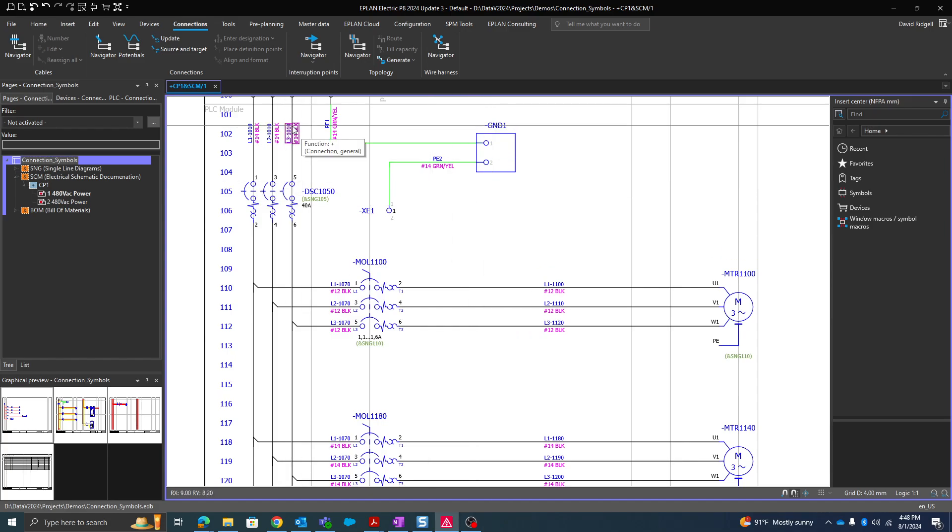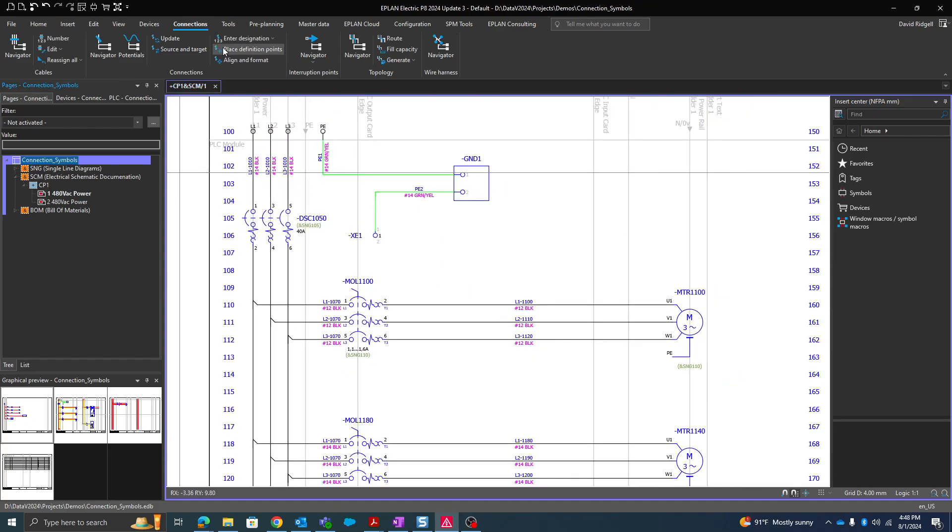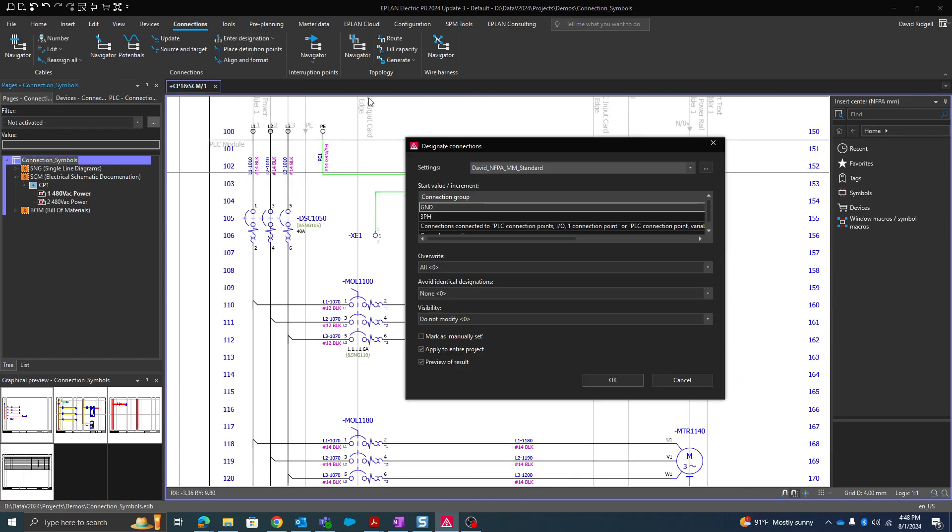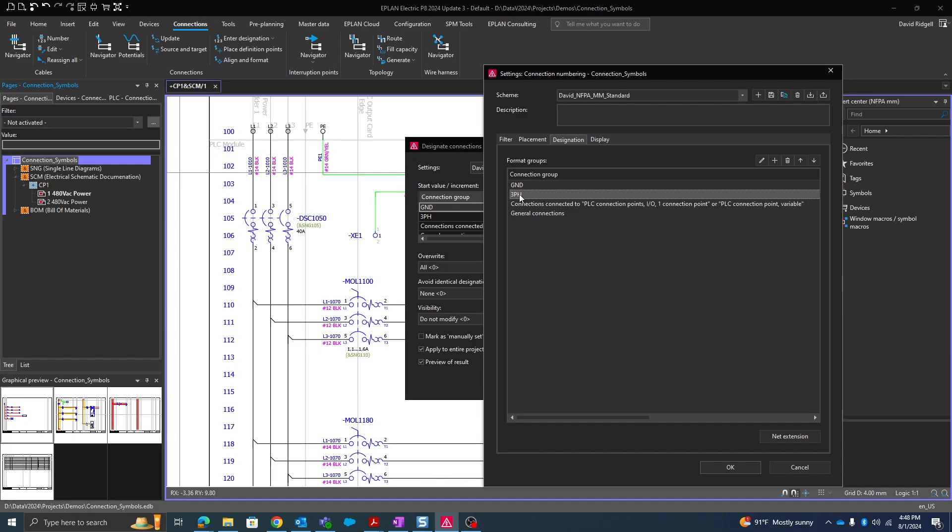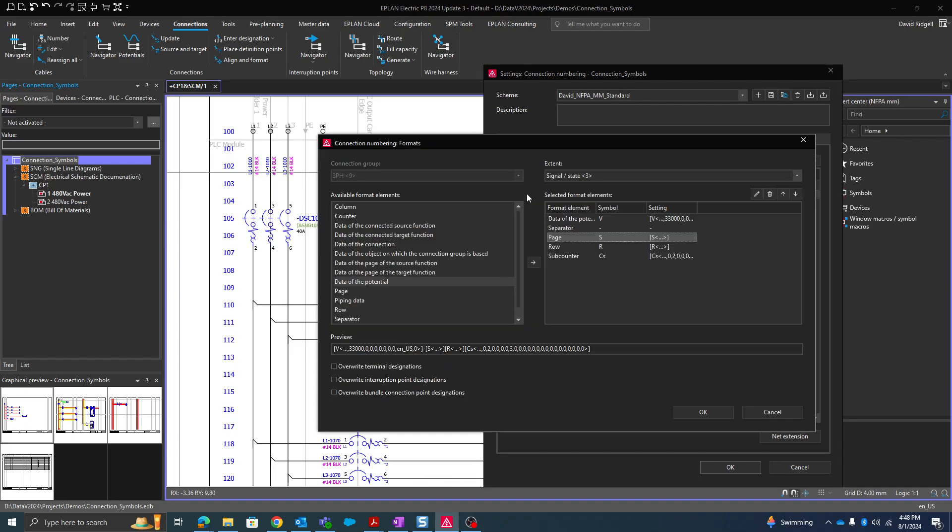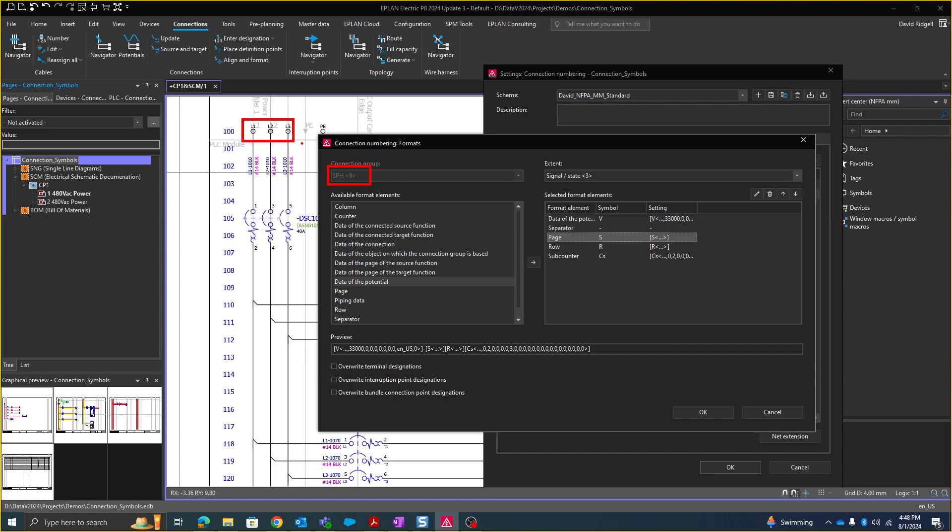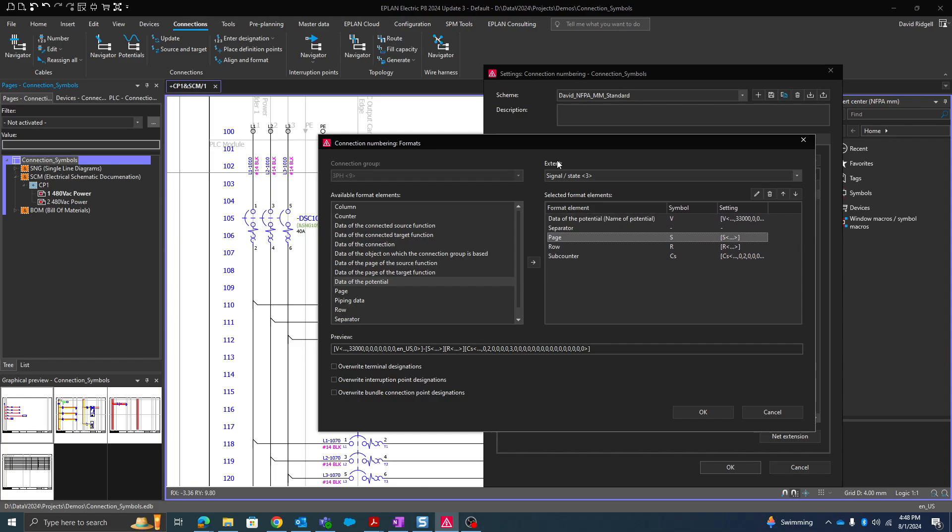Let's look at the wire numbering settings. I go to enter designation, click on the three dots. Here in the designation tab we have our different format groups. So let's look at the 3PH and make a modification. This is for our three-phase potentials. So this is the connection group, 3PH. That comes from the format property. Right now I have the extent set as signal state, meaning the wire number will change when the signal is broken. That comes from the signal isolation property at the symbol. So you can see that I have the data of the potential, a separator, page, row, and a subcounter.